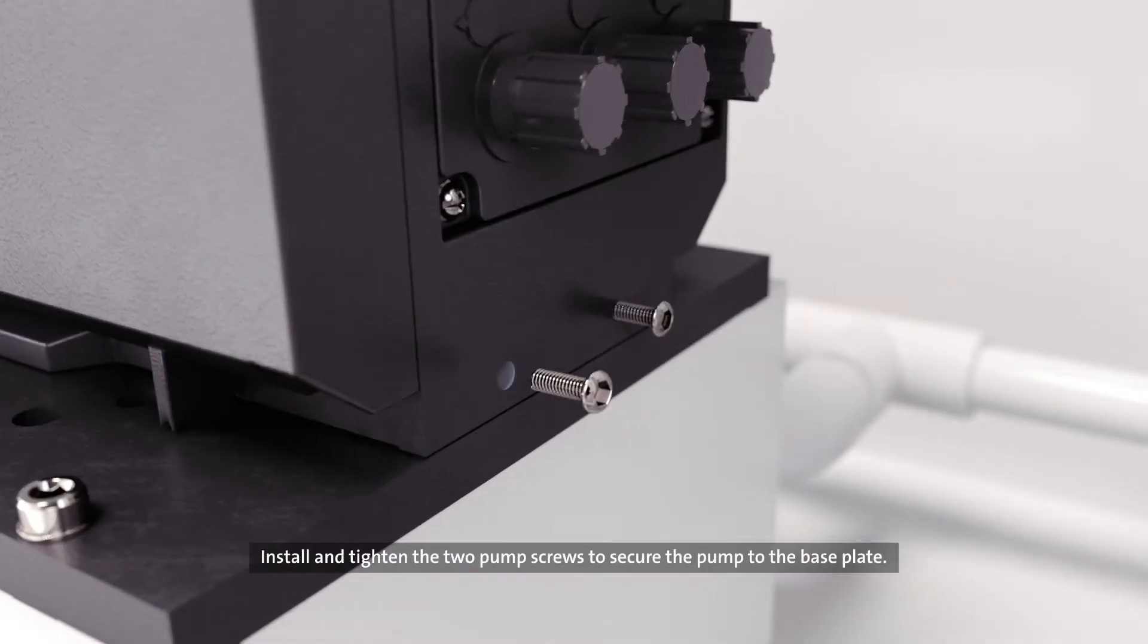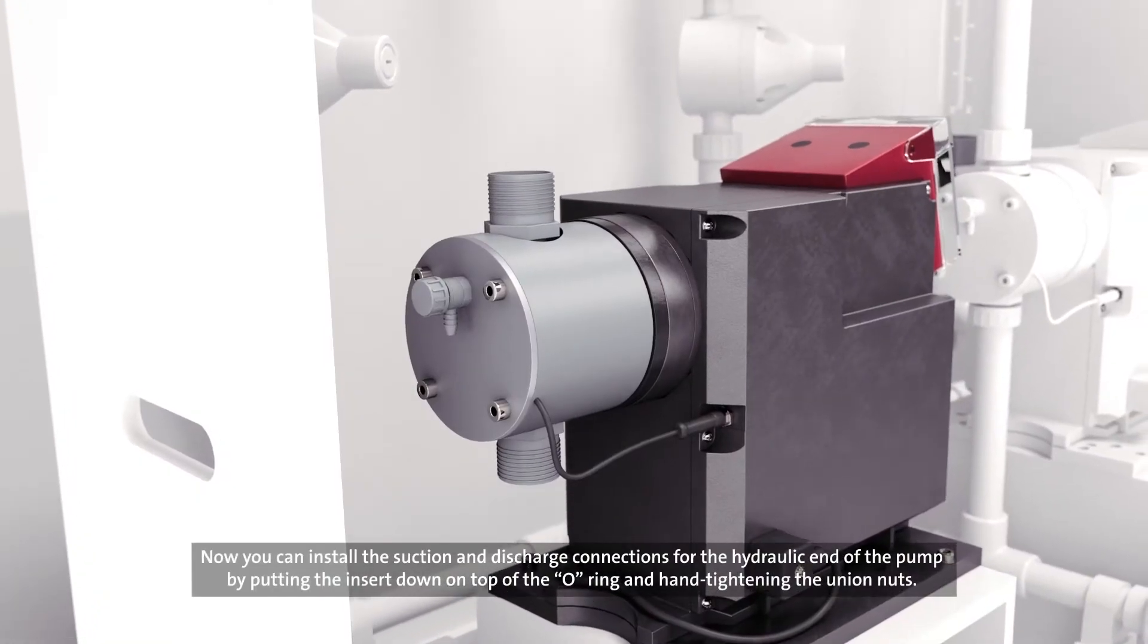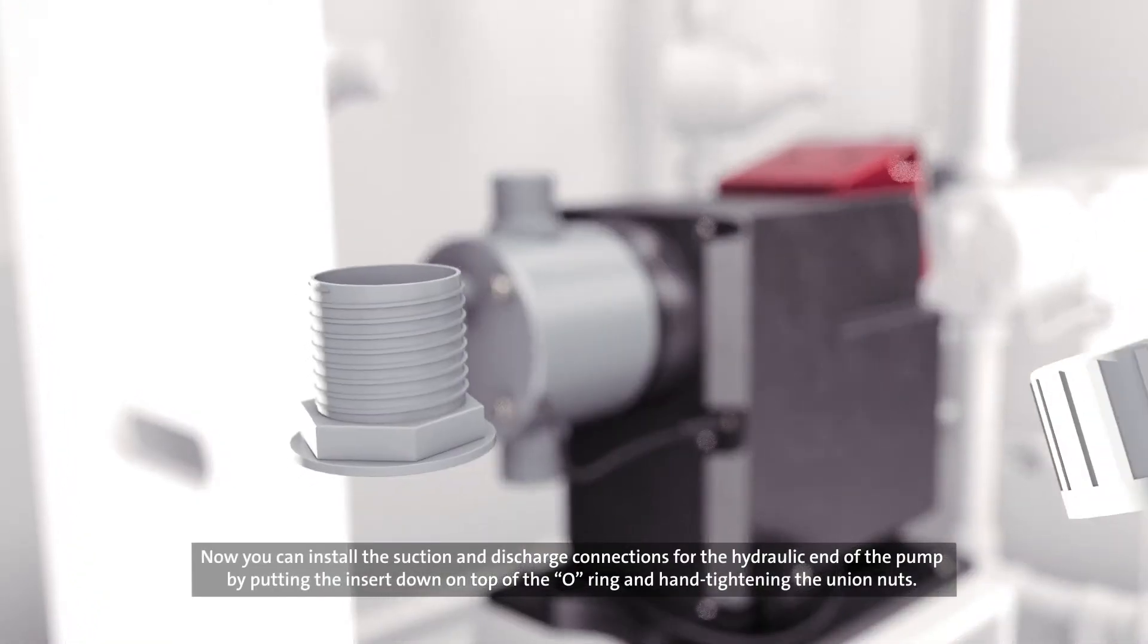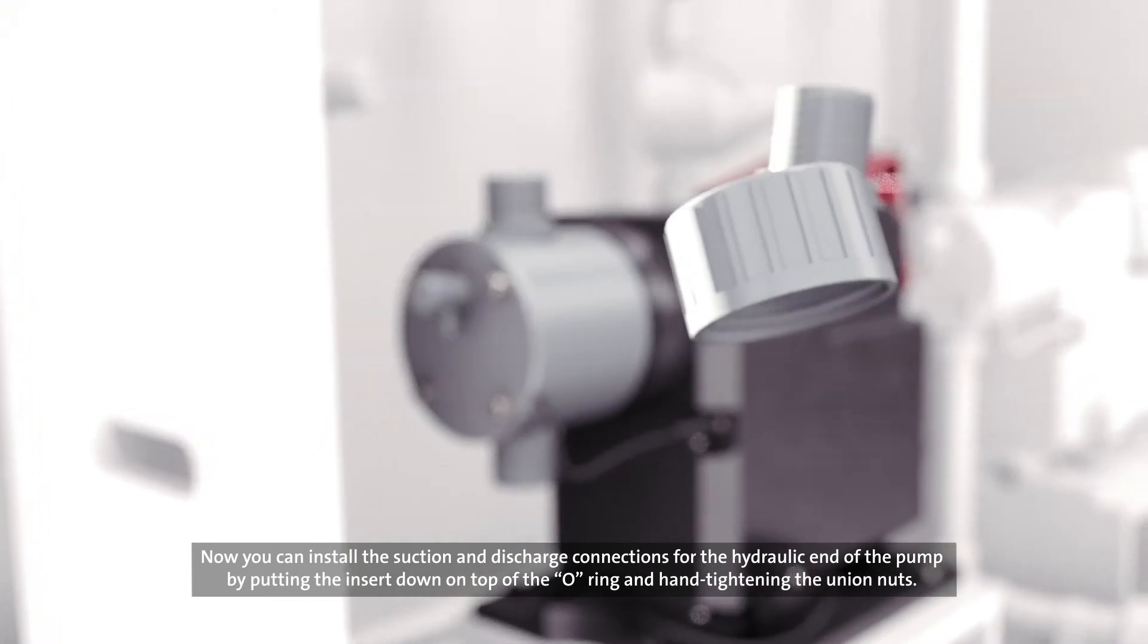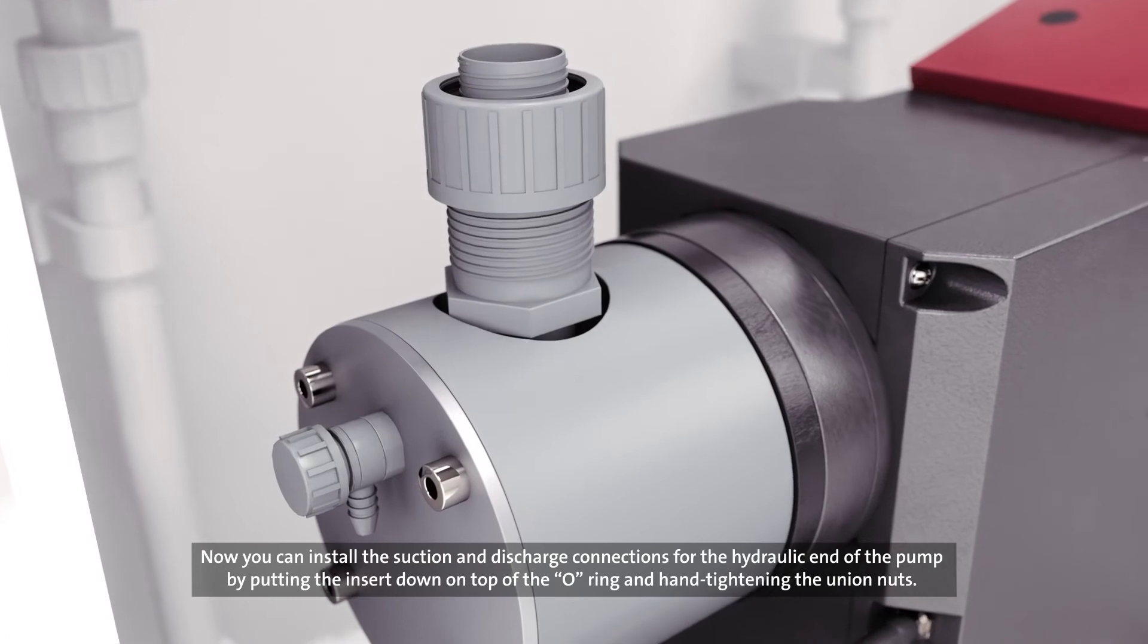Install and tighten the two pump screws to secure the pump to the base plate. Now you can install the suction and discharge connections for the hydraulic end of the pump by putting the insert down on top of the O-ring and hand tightening the union nuts.